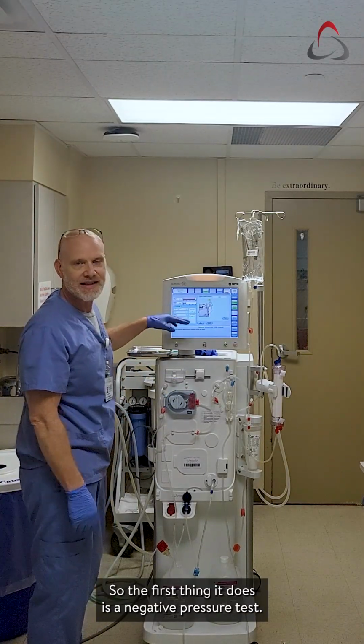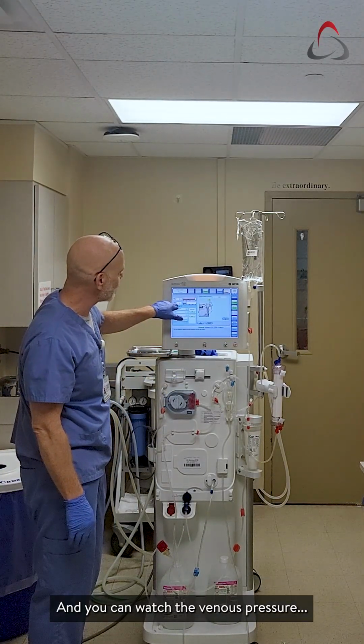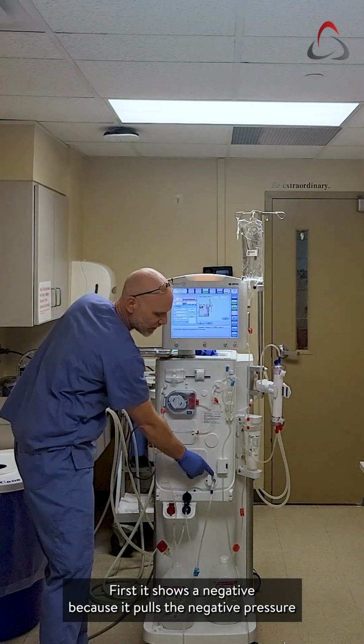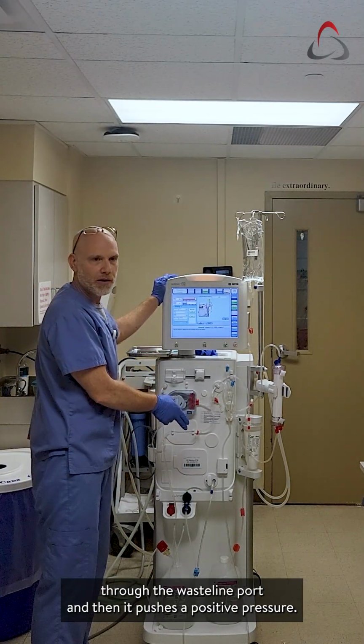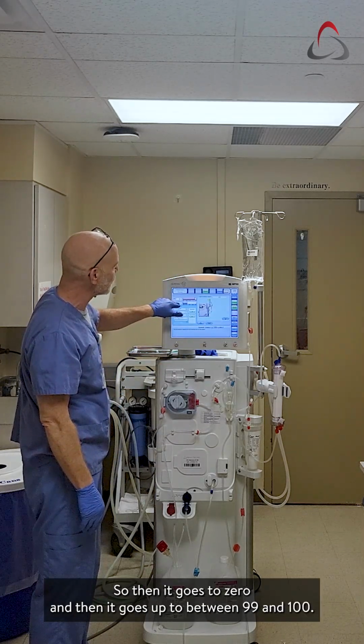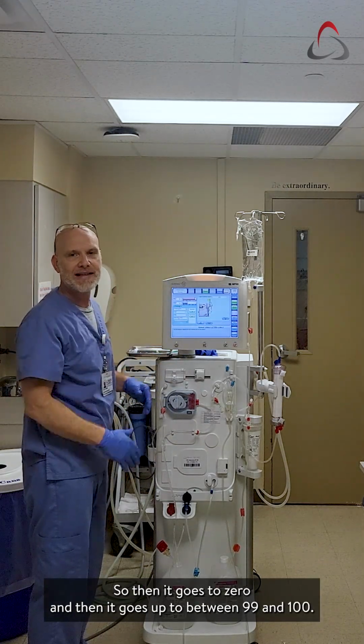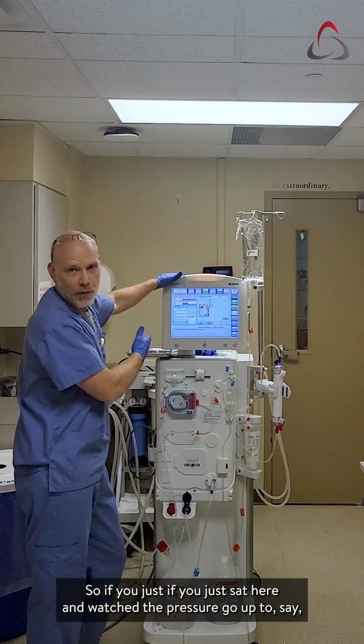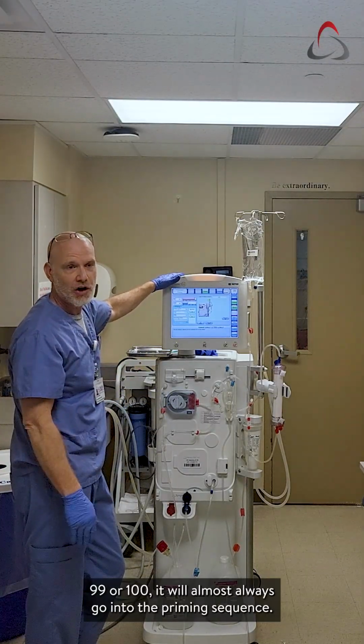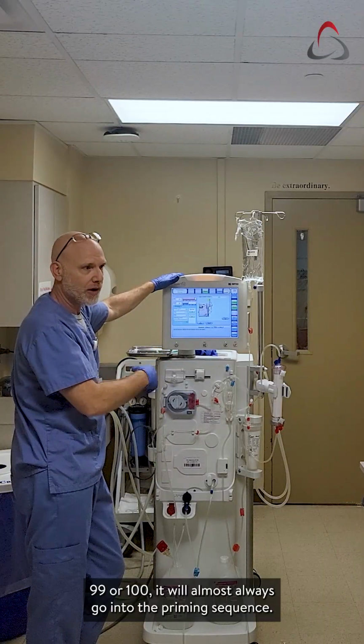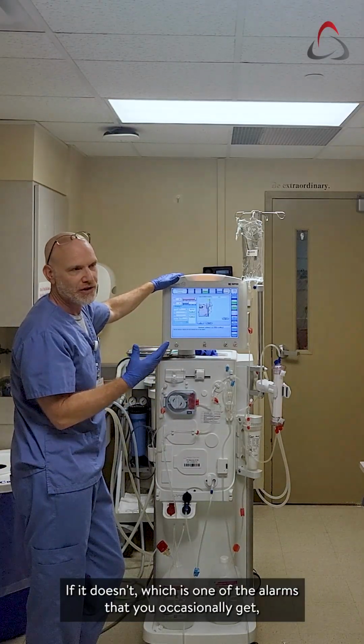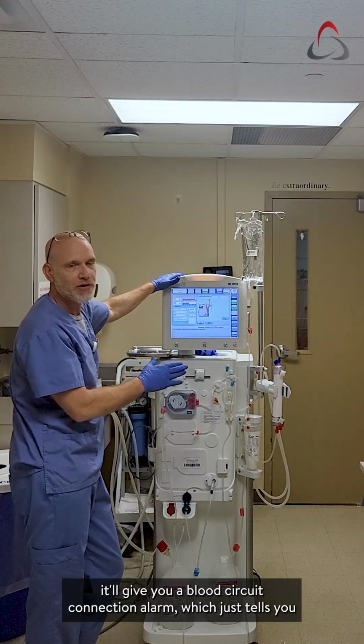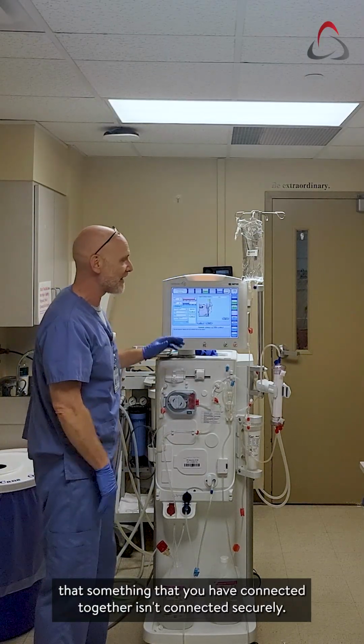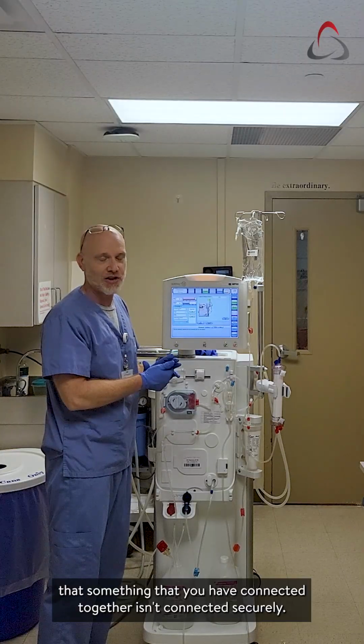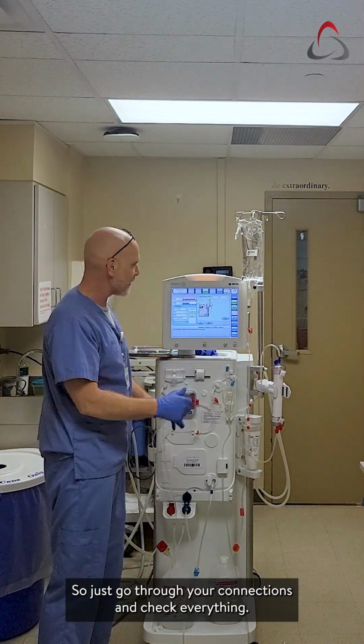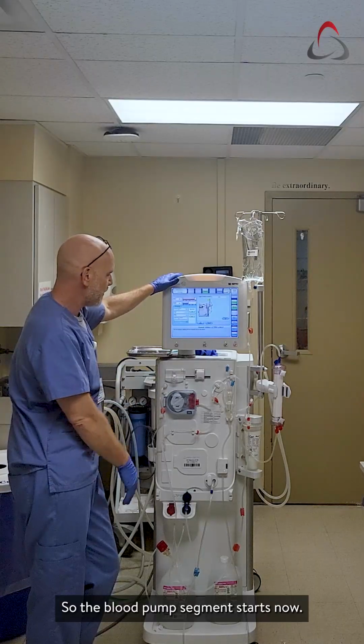So the first thing it does is a negative pressure test, and you can watch the venous pressure. First it shows a negative because it pulls a negative pressure through the waste line port. And then it pushes a positive pressure, so then it goes to 0, and then it goes up to between 99 and 100. So if you just sat here and watched the pressure go up to say 99 or 100, it will almost always go into the priming sequence. If it doesn't, which is one of the alarms that you occasionally get, it'll give you a blood circuit connection alarm, which just tells you that something that you have connected together isn't connected securely, so just go through your connections and check everything.